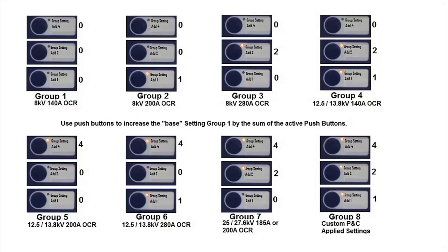These reclosers have 7 setting groups, which were programmed by P&C to accommodate the most common feeder protection requirements. There is also a Setting Group 8 option that is customizable in the event that Groups 1 to 7 do not meet the protection requirements. Field P&C must be contacted to program Setting Group 8.